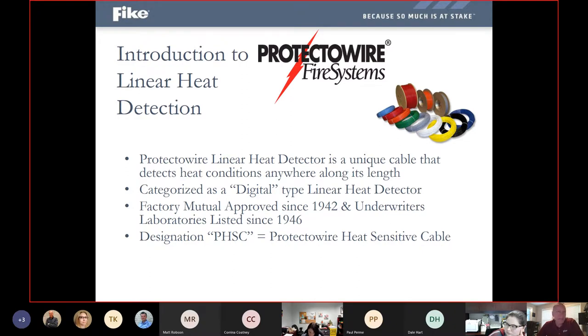So instead of having to put conduit and wire and boxes for traditional smoke or thermal detectors in an area, we can run this cable in and around anywhere that we want to monitor. And as soon as the heat increases to any programmed level, anywhere along that length of cable, it can be detected and put a system into alarm.